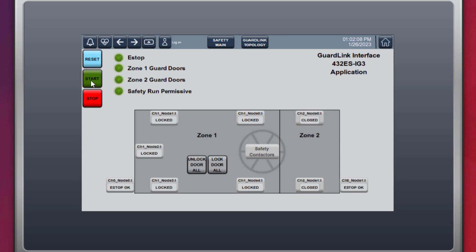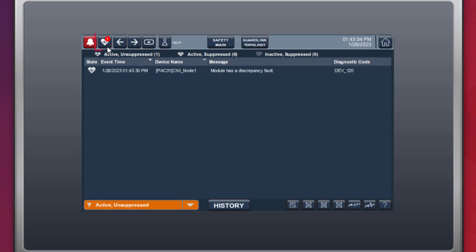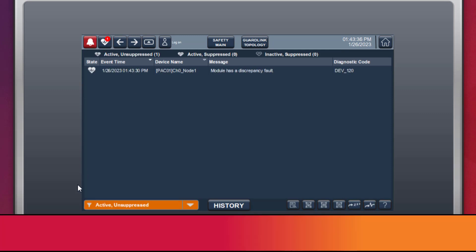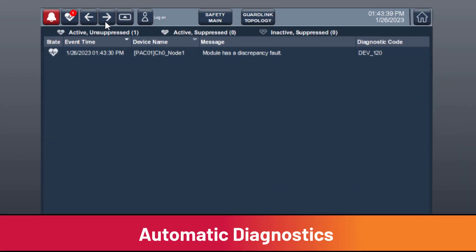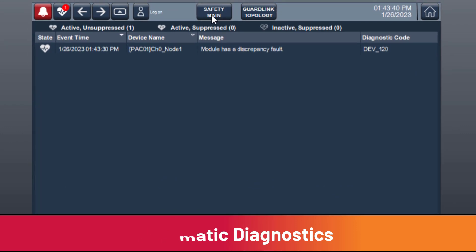With the machine running, a safety input has a wire fall off. The fault is clearly indicated at the e-stop node and in the alarm summary. If the programmer neglected to provide this level of HMI programming, automatic diagnostics still reports the GuardLink node that has a discrepancy fault.